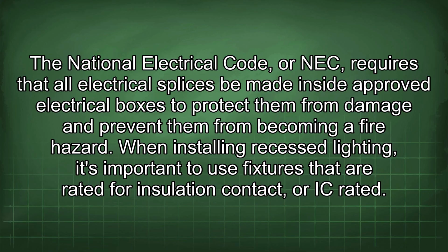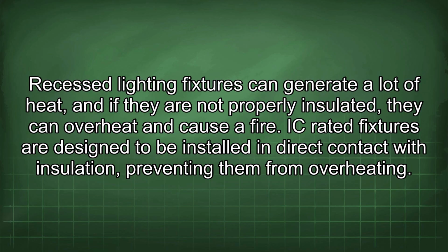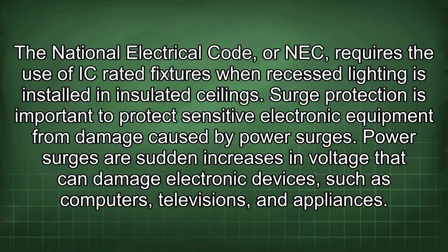When installing recessed lighting, it's important to use fixtures that are rated for insulation contact, or IC rated. Recessed lighting fixtures can generate a lot of heat, and if they are not properly insulated, they can overheat and cause a fire. IC rated fixtures are designed to be installed in direct contact with insulation, preventing them from overheating. The National Electrical Code, or NEC, requires the use of IC rated fixtures when recessed lighting is installed in insulated ceilings.